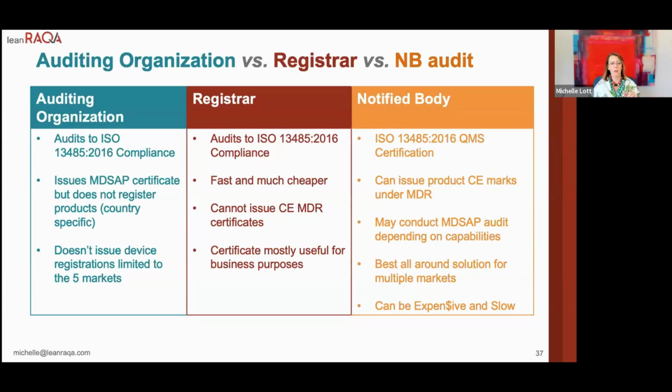And then, but it does not confer any kind of registration. Different countries take the MDSAP certificate different ways. Like I said, FDA does not accept the certificate, only the report. Canada only looks at the certificate and cares about the certificate.